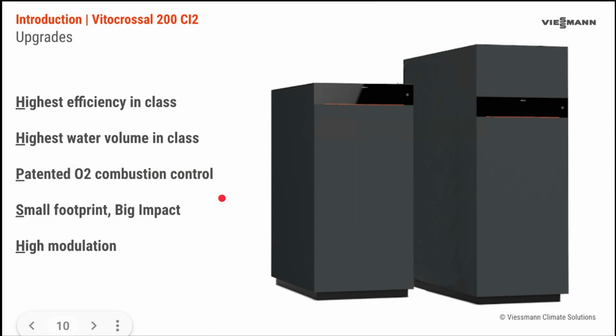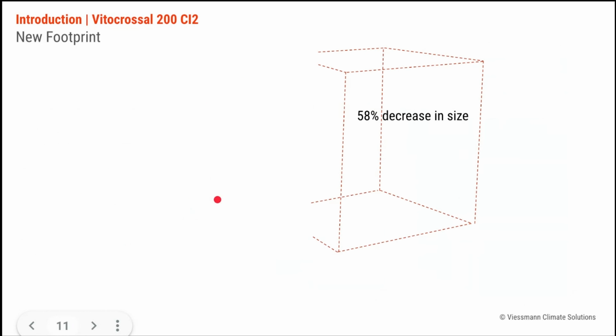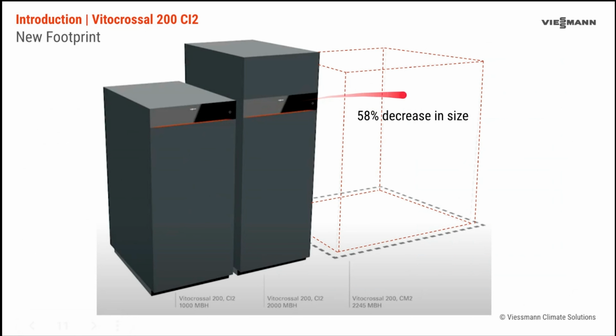So this boiler really addresses the fact that mechanical rooms are not getting bigger. We have a small footprint, but BTU inputs from 399,000 to 2 million, and then with the ability to cascade. And high modulation. Just an image here noting sort of a comparison to the CM2, the previous generation of boiler in this space. And we note a 58% decrease in size for similarly sized heating plants.